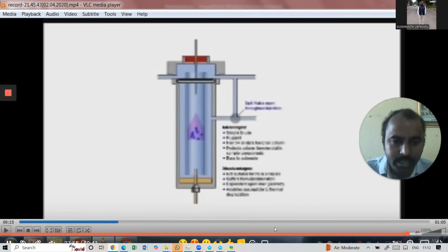Now if this analyte completely goes on to the detector, there is what is called detector load or detector cell load, which will completely choke the detector. Such techniques are not feasible or not allowed by any chromatographic system. That is why we use a vent system here, which will separate into two different paths, where the maximum portion of the analyte goes as waste and only a fraction of the analyte goes onto the detector. Let us see.